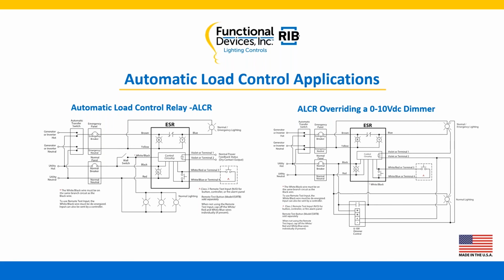Over on the right-hand side, we talk about the overriding of 0 through 10. So basically what's happening is over here, same circuit, our unit's actually controlling things the same way. But if you notice down below, what we have is a 0 to 10 volt dimming control panel down there. You notice we're controlling all those lights, those two lights out there. Normal lighting, we've got one up there, normal emergency lighting.